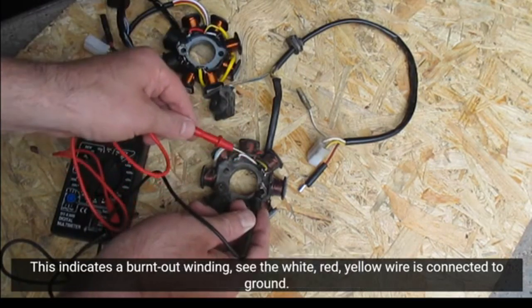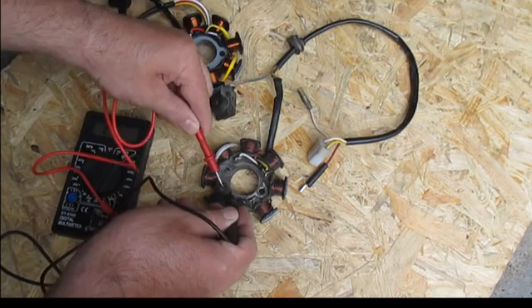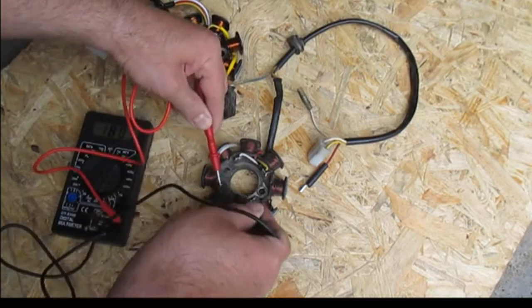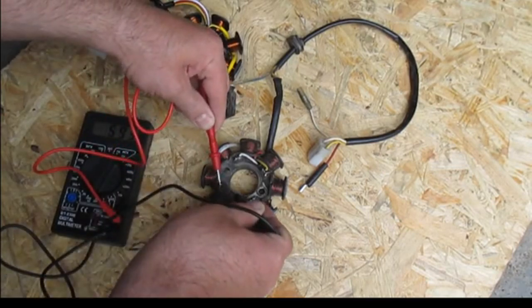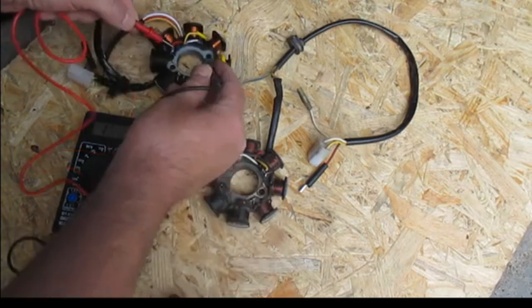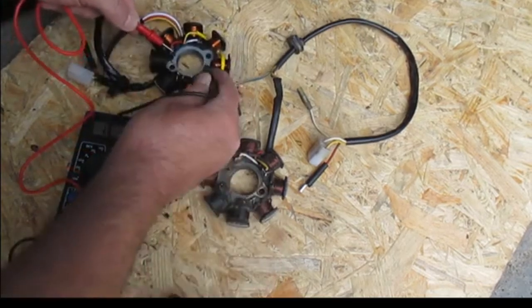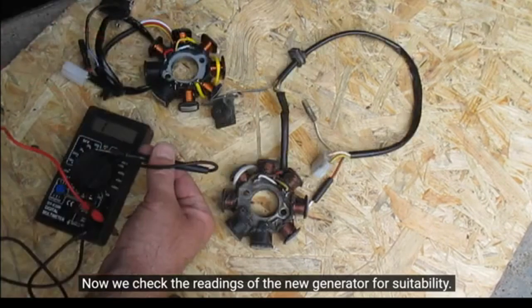Now let's move on to the old generator, and as we see, all contacts are shorted to ground, but this should not be the case. This indicates a burnt out winding. See, the white, red, and yellow wires are connected to ground.